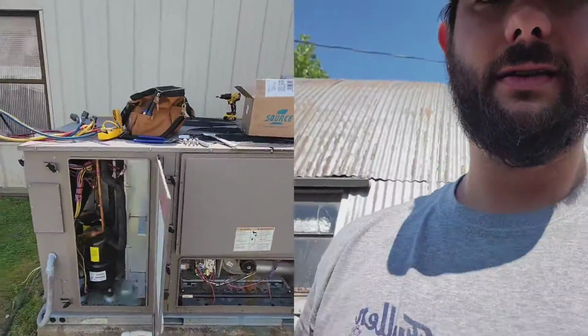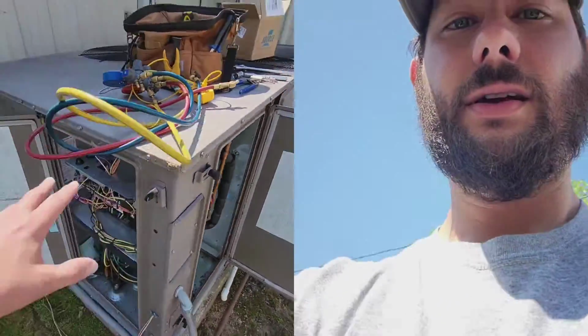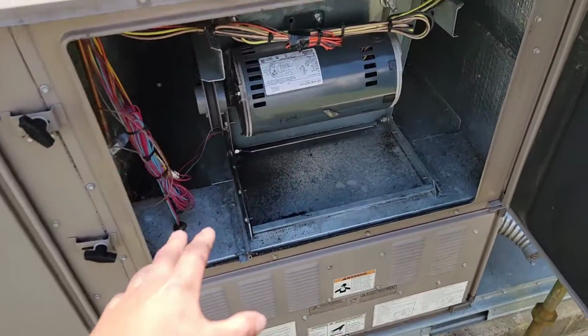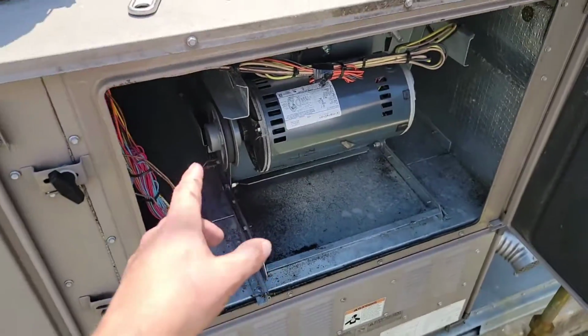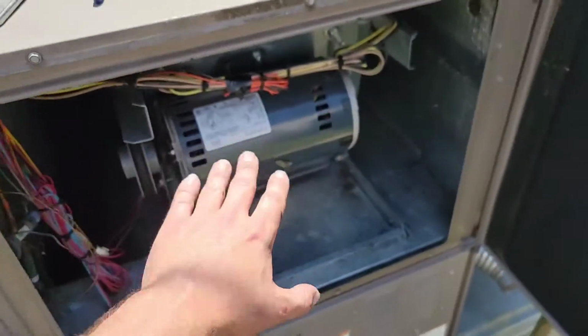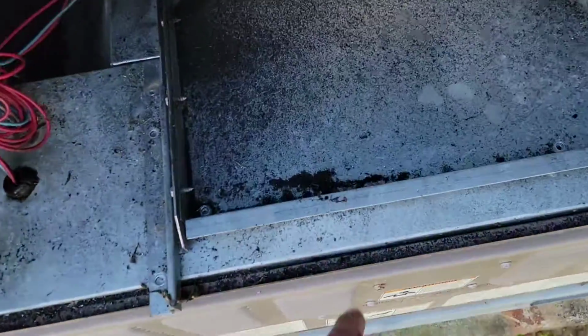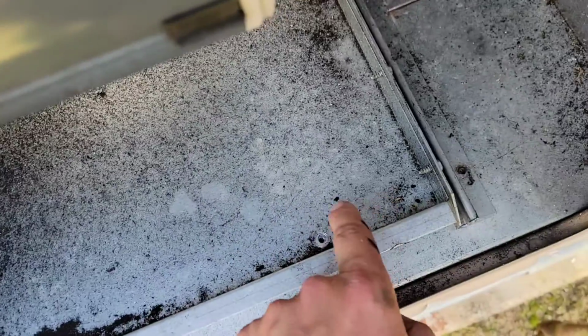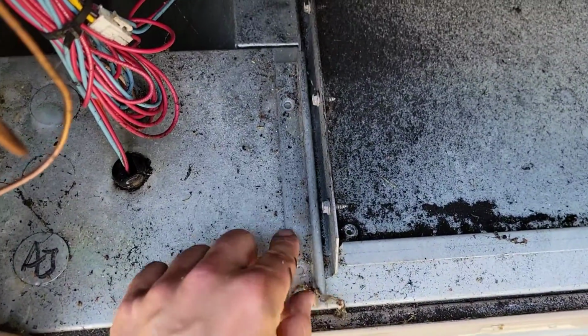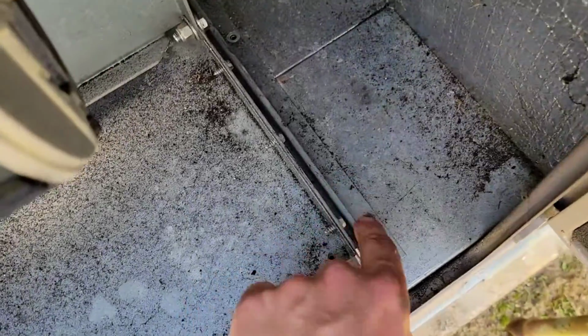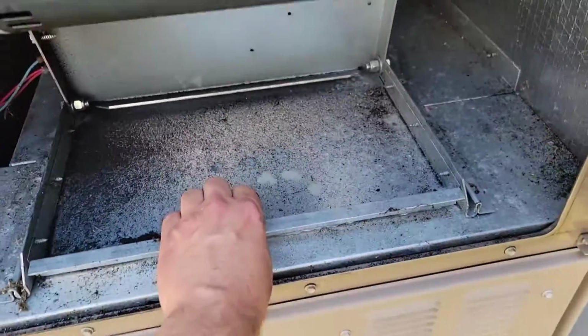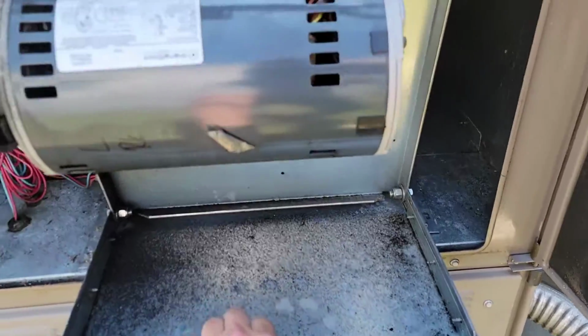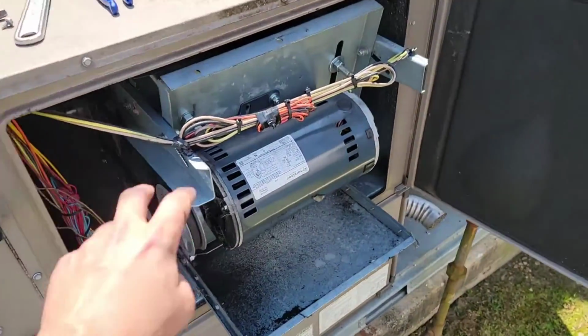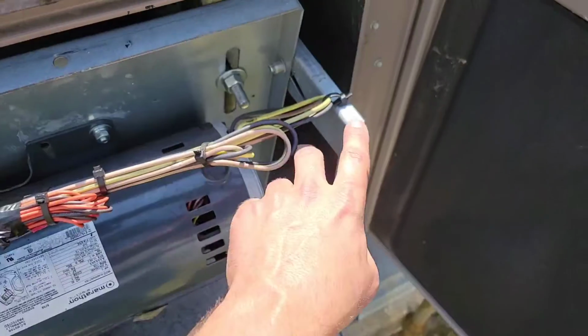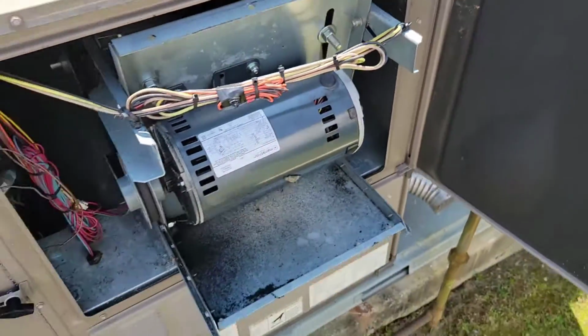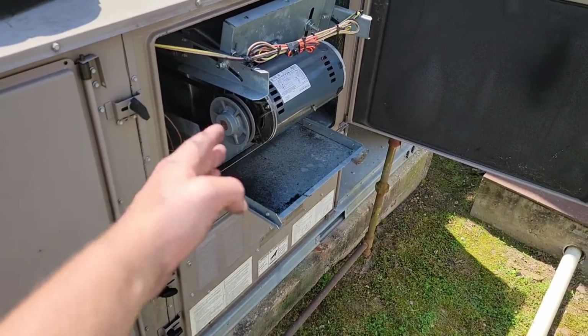And then you've got your separate sections for everything. Little bitty bonus for you. You want to be able to adjust the fan belt tension. You want to be able to work on the motor, make it a little bit easier on yourself. Loosen this screw, these 2 screws that hold this little bracket here, and then loosen these 2 screws. Once you do that, take your hand, pull this out. It's easier to work on that way. You might have to snip this wire tie and this one for the wires on the motor, but actually, you'll be able to pull the housing out.